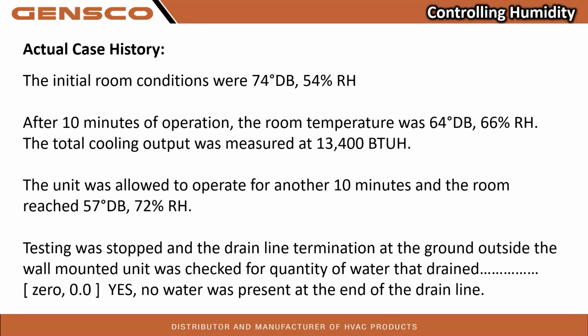I stopped the test, and I went outside before I left this house to check and see how much water actually came out of that drain line, which terminated near the ground. This was on an outside wall, went out the wall, down a piece of pipe to the ground, and there was zero water there. I dropped the temperature in the room, but didn't physically remove any water, and the humidity level went through the roof, and hence I'm going to have biologicals growing. And this is what produces the odor. In order to prevent that, I need the humidity to be a lot lower in that room.